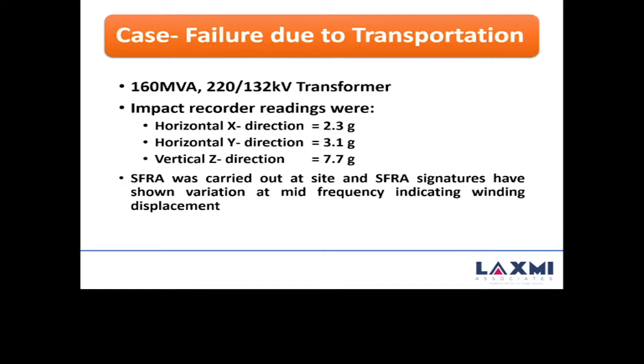which was giving 7.7 G in the Z direction. The base value is 4 G if you look at the impact recorder reading, but it is 7.7 G. That means we know the transformer has gone through some kind of vibration or jerk during transportation. Now, the first thing established, to find the reason for this high G, that is oscillation in the Z axis, is by SFRA.